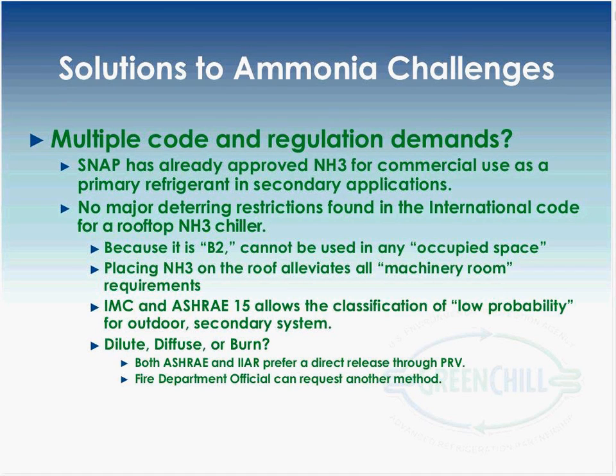wouldn't even be a doghouse on the roof with the chiller inside. It'll just be an outdoor system with removable panels for maintenance. It really would be truly an outdoor system. The IMC and ASHRAE 15 allow the classification of a low probability system if it is outdoors. So just kind of reiterating why we would put it outdoors, some of the benefits to that on the code side of things.